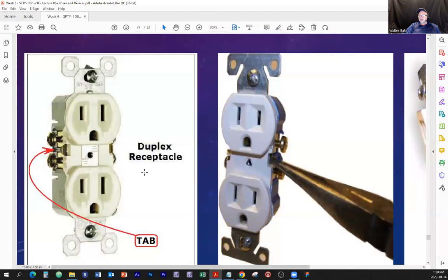And right now you can have 14-3, for example, or I would suggest maybe 12-3, because then you are raising the ampacity of the cable. Notice that the white one out of these three wires, white, black, and red: black and red will be the hot wires, and white is always neutral. The white one will be the busiest one of them all.